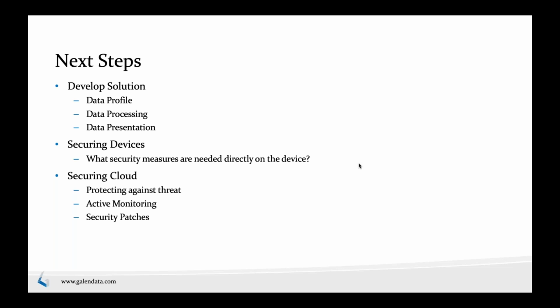How do you apply security patches, because a lot of this is going to be developed on third-party systems, somebody else's operating system, somebody else's libraries? How do you constantly know that their security patches are being released, and how do you apply them in a way that does not interfere with your delivery of your care or your therapy or whatever is the device function?